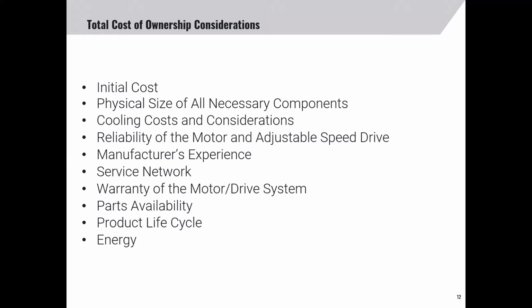Unfortunately, there are no perfect manufacturers, nor are there any perfect products, so problems will eventually occur. But before those problems occur, and hopefully before the product is even purchased, it is critical that you consider a manufacturer with a sufficient installed base to support an extensive network of service, including readily available spare parts in order to help minimize your downtime. Another consideration is the warranty or lack thereof. Does the manufacturer offer an extended warranty on both the motor and the drive? Does the manufacturer even offer both motors and drives? Having single source responsibility can eliminate finger pointing, which will minimize delays in problem solving, thus minimizing downtime.